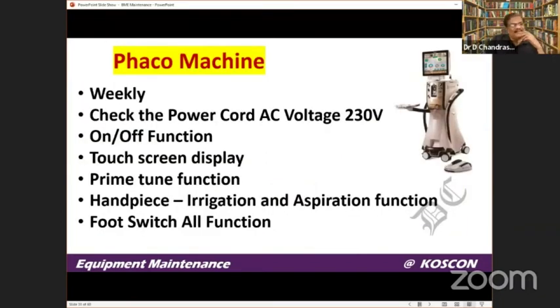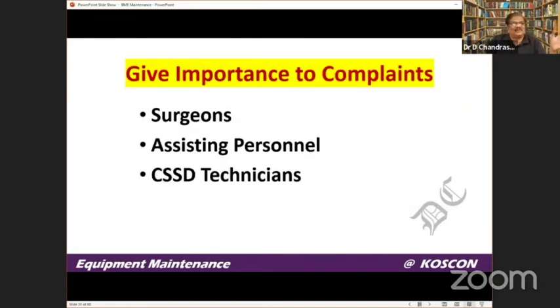The Phaco machine is checked at least weekly because of heavy usage, and it's very critical that it should not stop during functioning. This includes checking the touch screen display, prime tune functioning, handpiece, and irrigation and aspiration function.